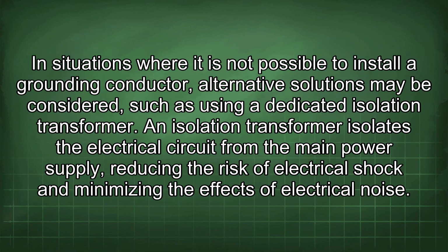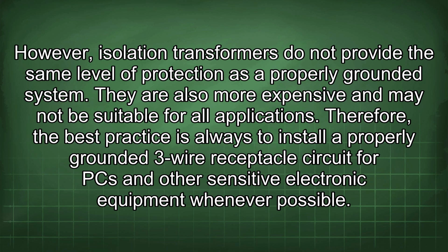In situations where it is not possible to install a grounding conductor, alternative solutions may be considered, such as using a dedicated isolation transformer. An isolation transformer isolates the electrical circuit from the main power supply, reducing the risk of electrical shock and minimizing the effects of electrical noise. However, isolation transformers do not provide the same level of protection as a properly grounded system. They are also more expensive and may not be suitable for all applications.